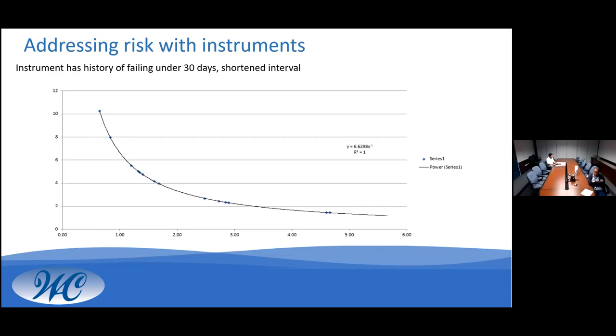Therefore, the algorithm calculates its due date with a tightened function. Should this instrument be found with a near perfect score, instead of 30 days default, it will return for calibration within a week. But what happens if it continues to have a good score? If no further pre-cal failures are detected, the algorithm assumes lowered risk and slowly increases the max days allowed. So instead of 10 days max, probably the next time will be about 14.